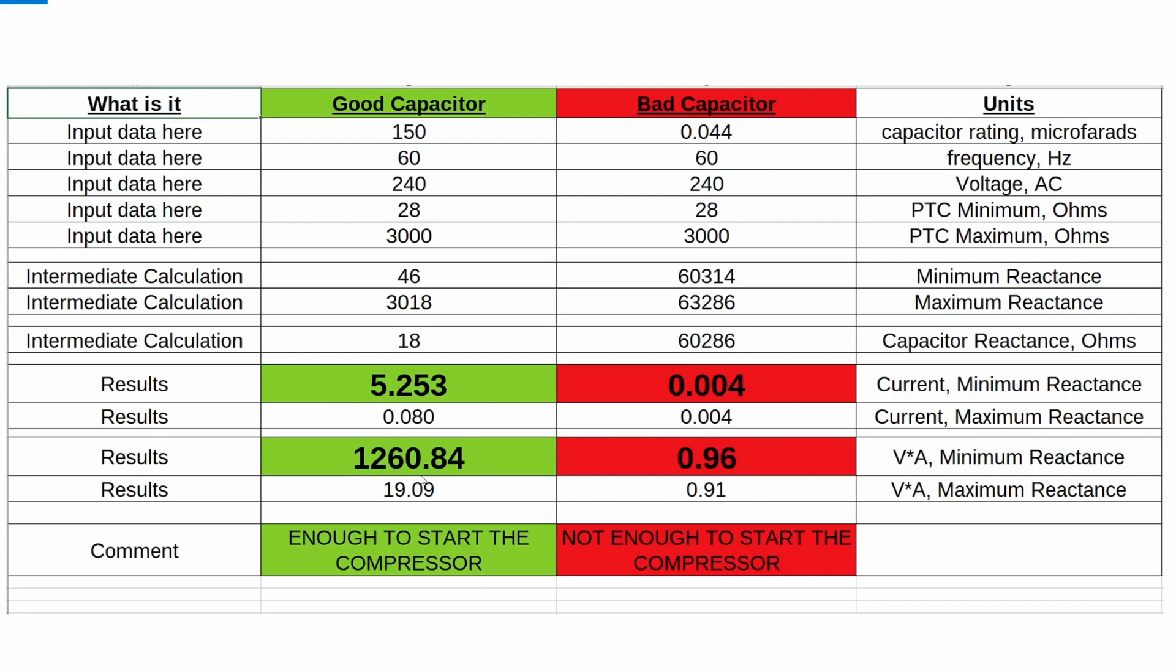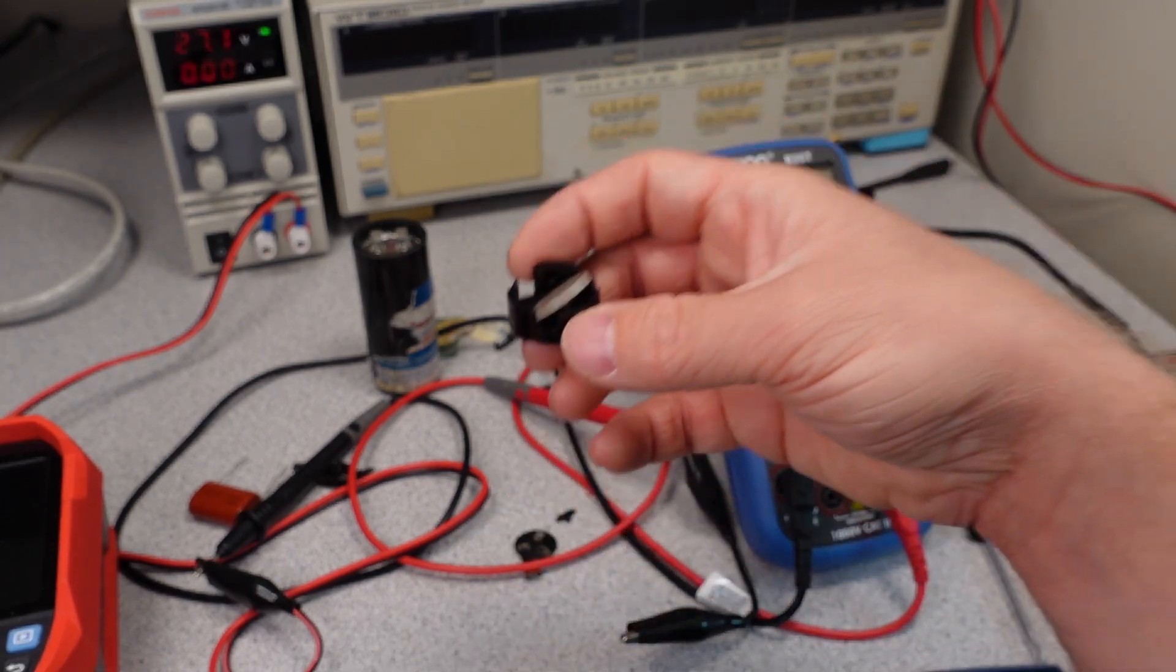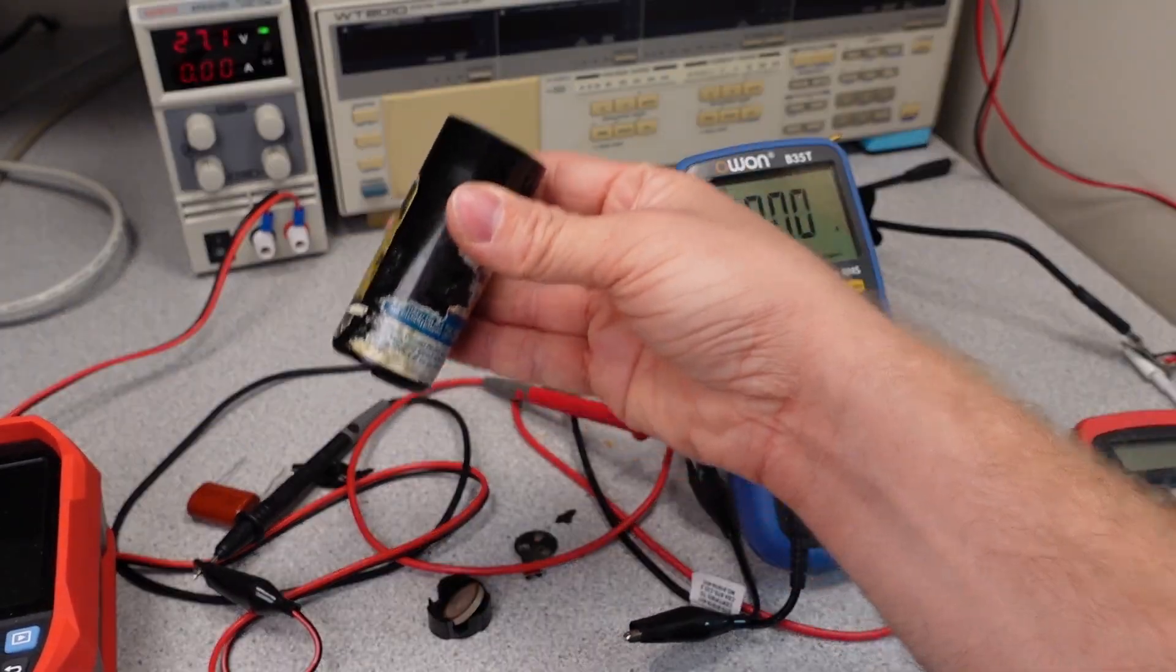When the compressor is running, the capacitor is effectively out of circuit. Just a few milliamps of current are running through it. But when it starts up and that PTC is cold, we have a high current and a lot of VA running through, which is enough to push the compressor into rotation. So this little device, as it gets hotter, the resistance gets higher, and therefore it disconnects the capacitor, which is totally cooked.